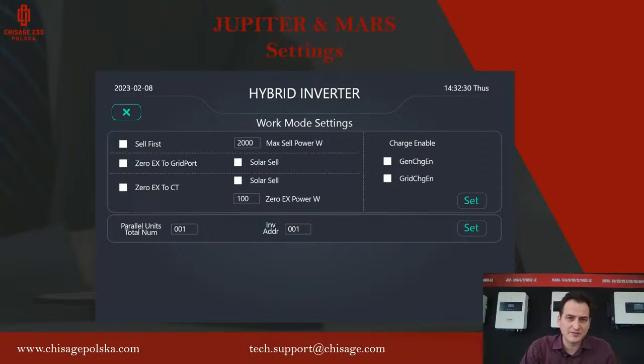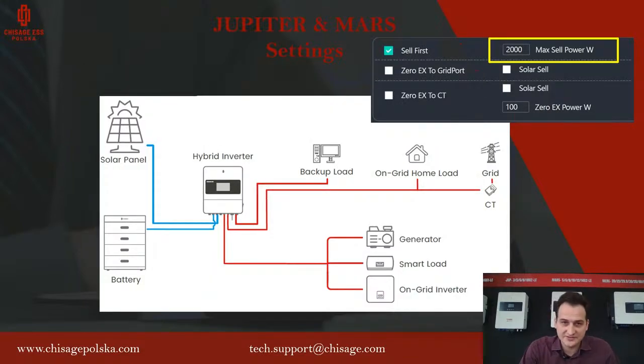And if we're talking about working modes, we have 3 working modes. We'll start with sell first. Sell first means that the inverter will sell all energy from solar panels and from the battery up to the value we put in this yellow frame. So now it's 2 kilowatts, 2000 watts. So the inverter will try to sell 2000 watts. If it cannot do this from solar panels, it will also try to sell from the battery. That's basically a mode very similar to an on-grid inverter.